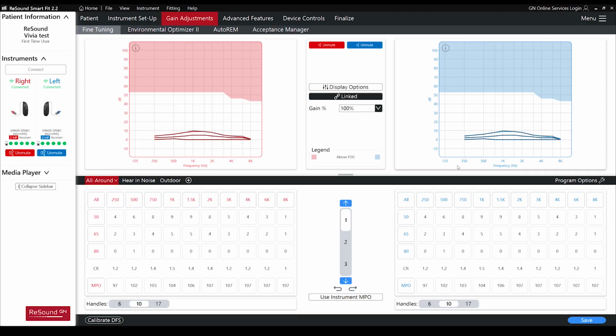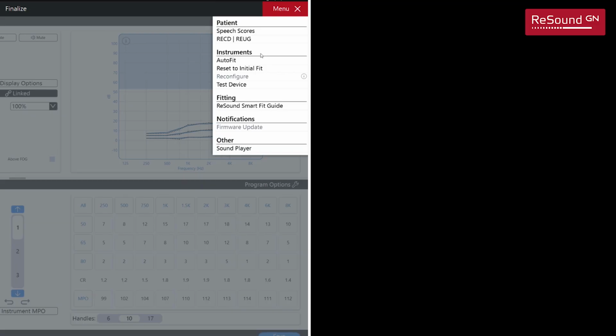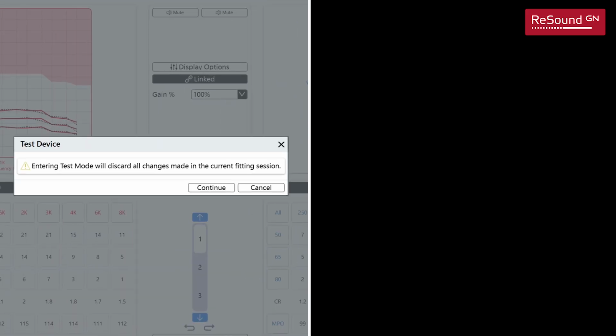To access test device in the fitting software, the process is still the same. Go to Instrument and select Test Device. Or if you prefer, you will also find it in the hamburger menu. What happens next is different. Until now, the first thing you saw was a scary message telling you entering test mode will discard all changes you made in the current fitting session.